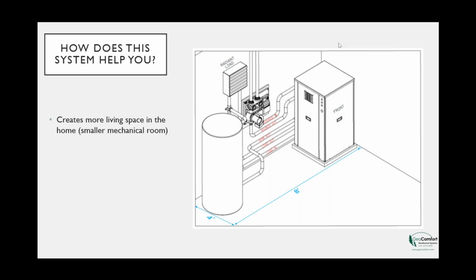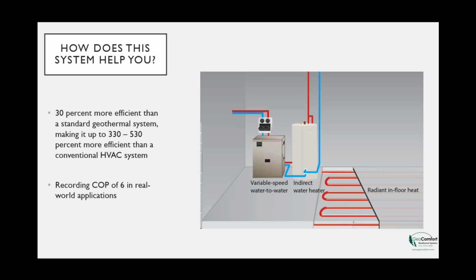And the fact that we've eliminated a lot more components in the system because of this technology means we can make the mechanical rooms much smaller. And we all know what it costs to build a home and the cost per square foot. So if we can create more living space by having a smaller mechanical room, that really does help out the homeowner. And you can see there that we're at about a 32 square foot footprint in the mechanical space or less, depending on what you're doing. Now this shows the hot water option. So that's the domestic hot water tank that you're seeing there. For those of you on the webinar who might think that's a buffer tank, it is not. That's your domestic water heating system.